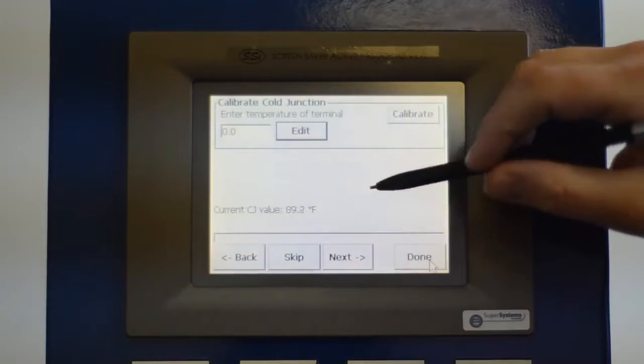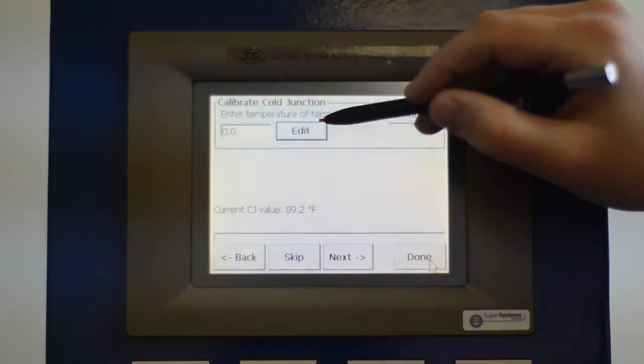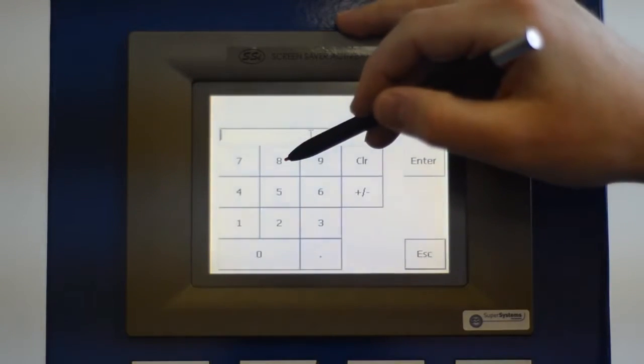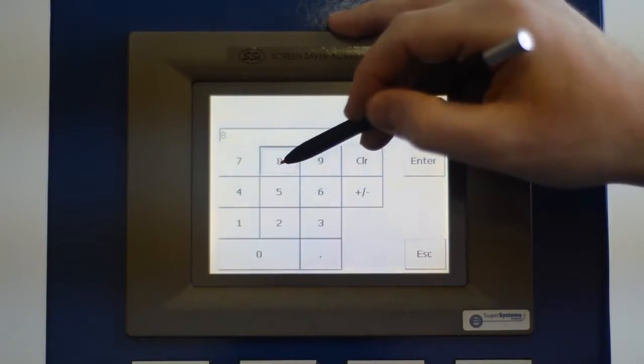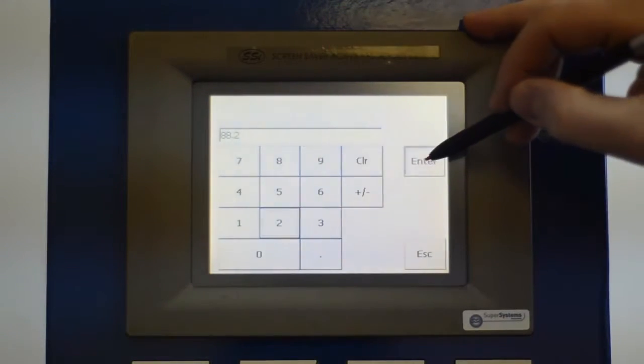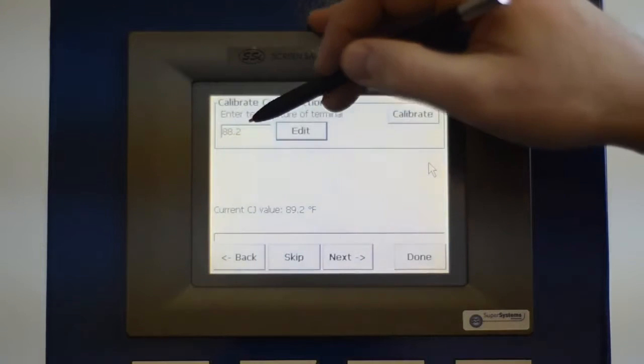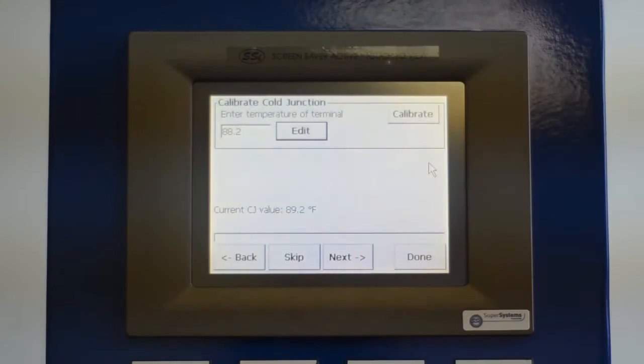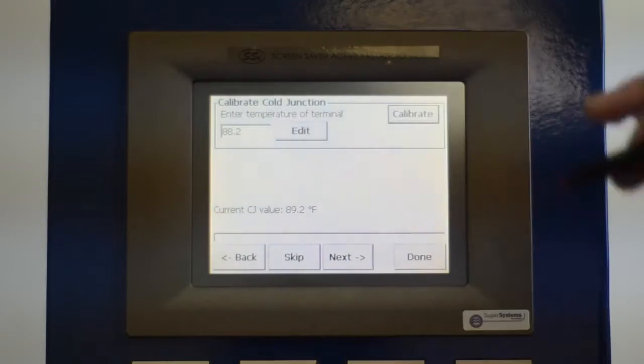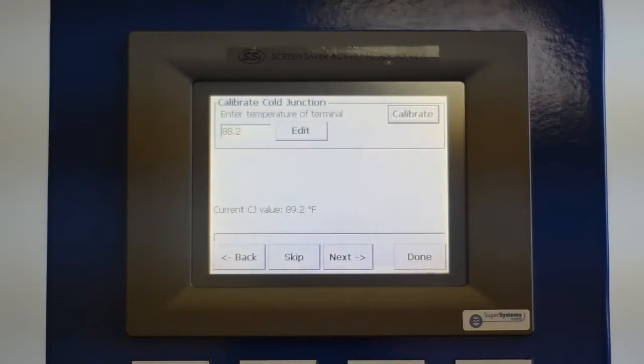So let me go back here. We're reading, in this case, 89.2. So I'm going to subtract 1 degree from that, say 88.2, enter. So this temperature now is what I want to tell it that the temperature is at the cold junction, and I'm going to select calibrate, and we will give it a minute here to start the procedure.